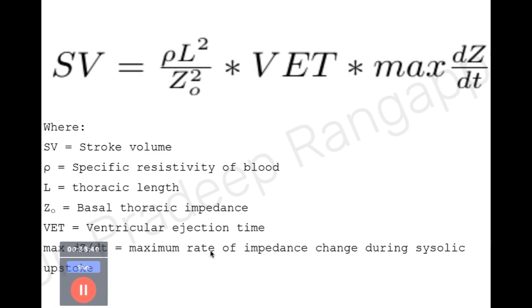Basically, you are looking at the difference in the resistance from one part of the chest to the neck, and you understand that by the low impedance structures within the body, which is the blood flow system. So your impedance is inversely proportional to the total fluid content which is conducting the current in that part of the chest where you have placed the electrodes.